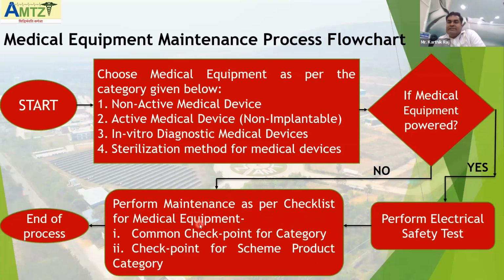So the best thing is that once the equipment is inside the hospital and you are using it, you use the IEC 62353 testing standard. Once you test it, you will know the leakage current, enclosure leakage current, patient leakage current, all those factors, and you are seeing whether all are within the safe limit or not. If so, then you will perform the next step. That is, if the equipment is not powered, it also goes to the checklist part.